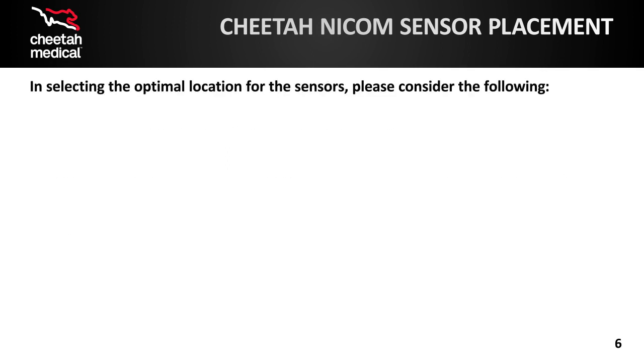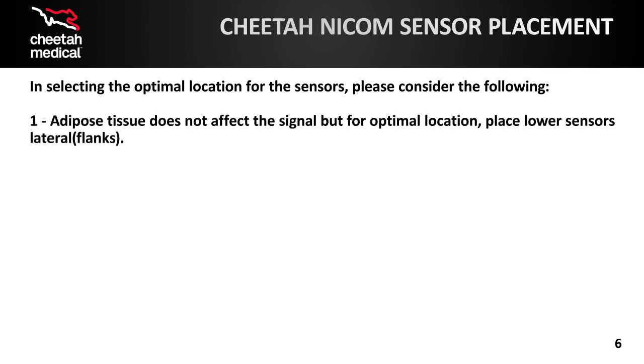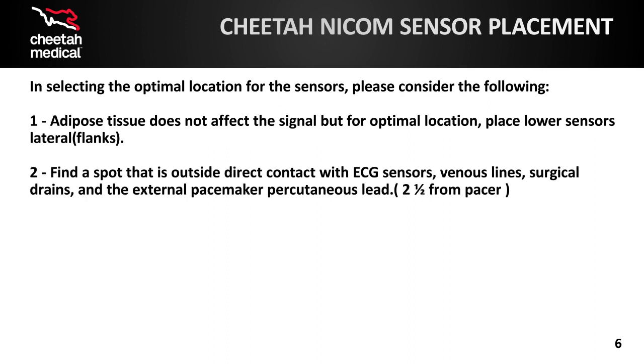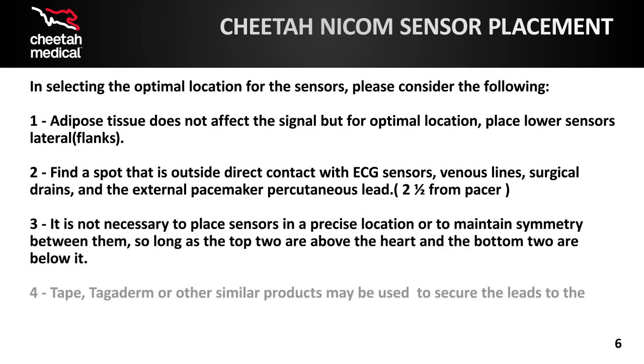In selecting the optimal location for the sensors, consider the following. 1. For optimal signal quality, lateral location is preferred for the lower pair, especially in obese individuals. 2. Find a spot that is outside direct contact with ECG stickers, venous lines, surgical drains, and the external pacemaker percutaneous lead. 3. It is not necessary to place sensors in a precise location or to maintain symmetry between them. 4. You can also use tape to secure the leads to the patient.